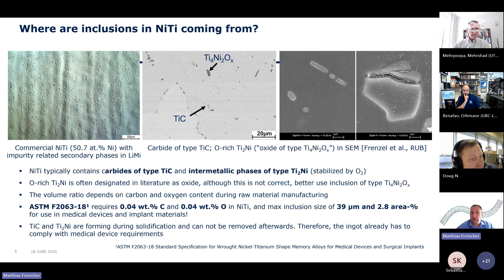ASTM F2063 specifies the carbon and oxygen content for use of the material in medical applications, and you can see the threshold values, which are 0.04 weight % for both of them. It also specifies the max inclusion size, which is 39 microns, and the expected max area fraction at a given magnification, typically 400 to 500x, which should not be larger than 2.8 area %.